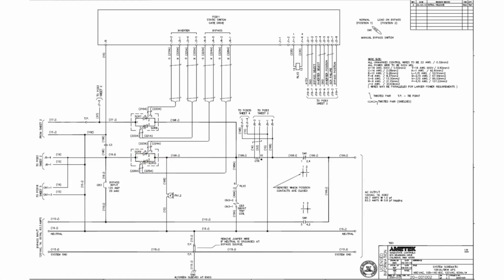Because you have to remember that the inverter, so this one here, synchronizes itself with the bypass supply here. It's always trying to stay with the bypass supply as long as the bypass supply is within tolerance. So that means frequency, phase displacement, and voltage. If the bypass is within tolerance, the inverter will do everything it can to stay in sync.